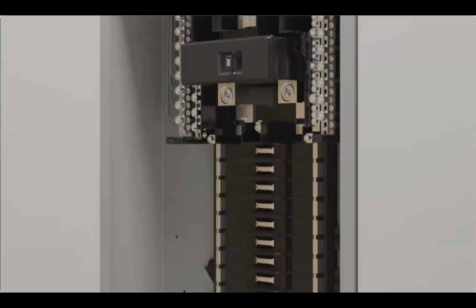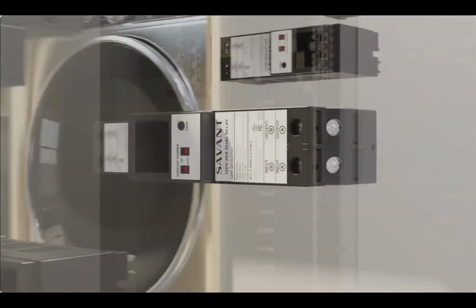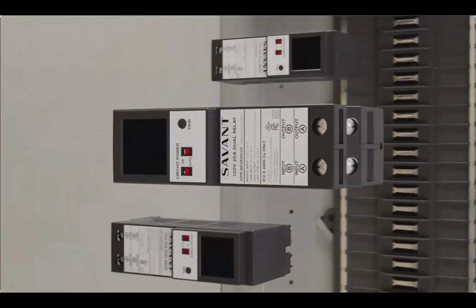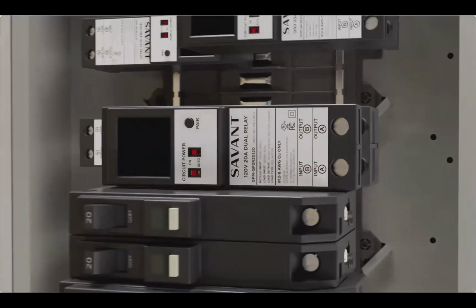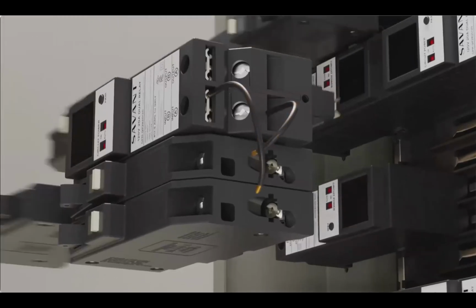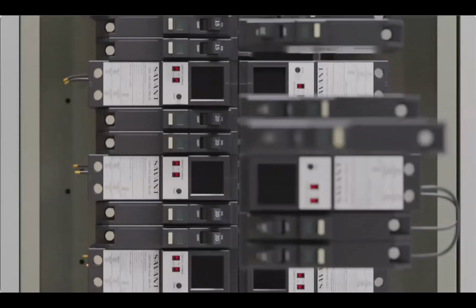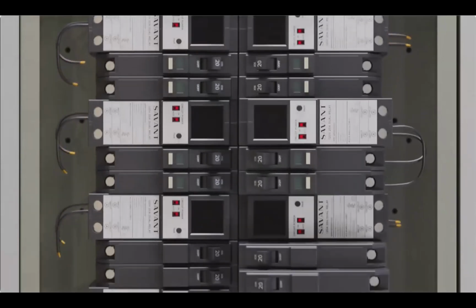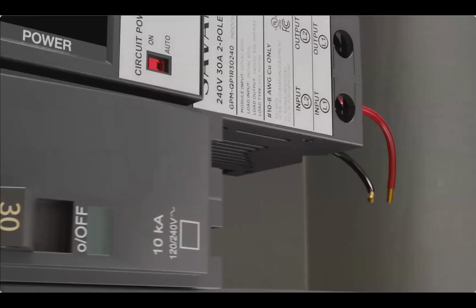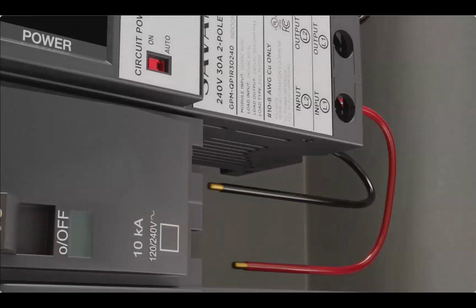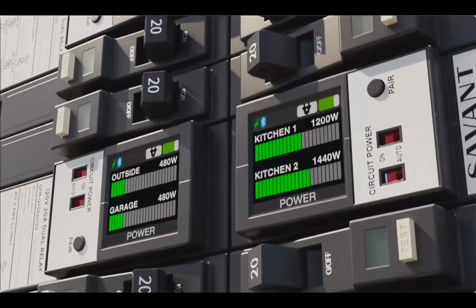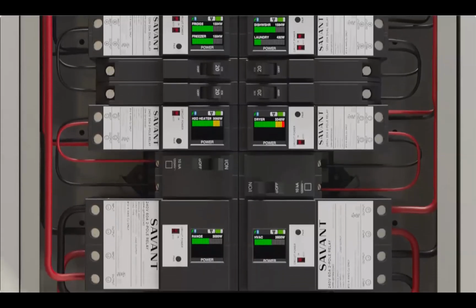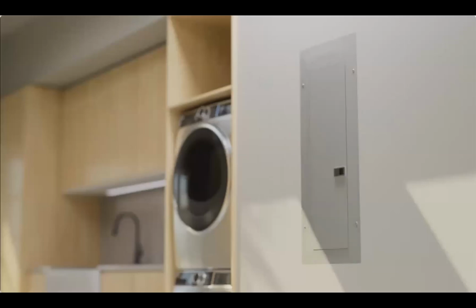So here's the standard panel. We don't think you can hear the audio, but you can see these modules go right into the panel. They snap in pretty easily, and you see that the breaker actually feeds the module. Each module, depending on the type, will have two circuits, and the output on the module goes to the load, whether it's lighting, a refrigerator, or anything connected to the panel.